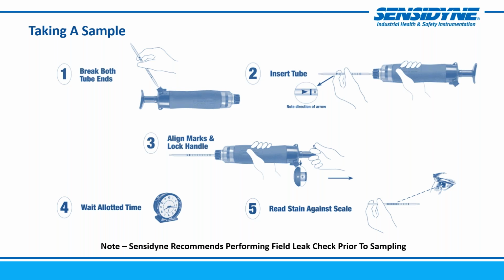Each detector tube has a wait time allotted. The wait time is there because a chemical reaction is taking place. So once the gas constituent in question comes in contact with the reagent, that's the amount of time required for the reagent to react properly and show the color change. And then lastly, you can remove the tube from the pump after that wait time, and read the stain against the scale that's on the tube.